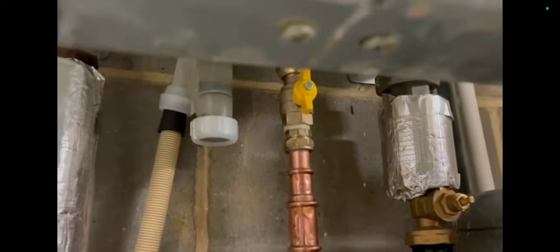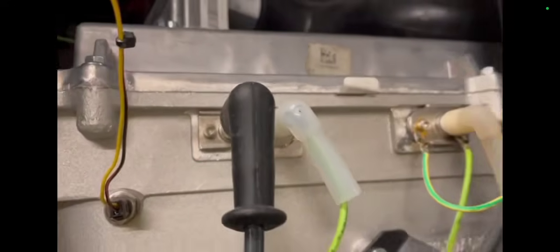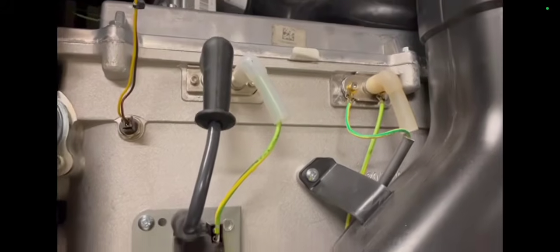So I know that these tend to get flame loss when either there's no gas to the boiler or insufficient gas, or the condensate's blocked, or that there's a problem with the probes, or the burner needs a wash down. So I didn't want to go into the burner. I could, but that's going to be my last resort because that's the hardest thing to do.